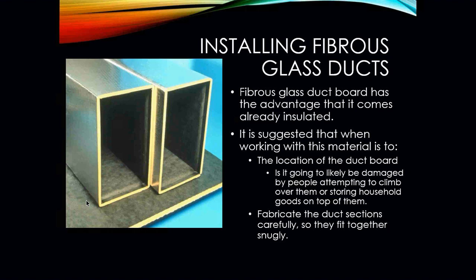So your fiberglass duct sections have to be carefully cut. They have to be taped. They have to be stapled. And if they are going to be exposed, they have to be somehow protected so that it doesn't start to collapse. However, this type of ductwork has been known over years, especially if it's been in the attic for years, to just simply deteriorate on its own and eventually just comes out anyway, and metal ductwork gets put in.